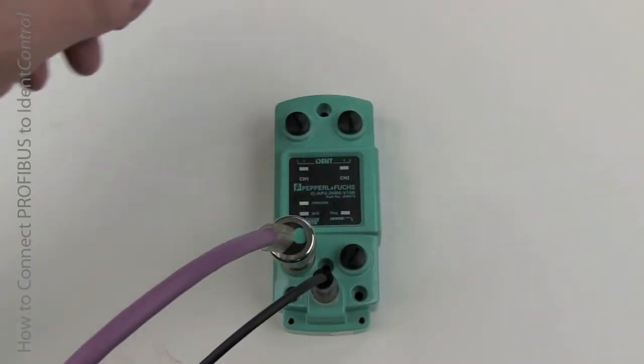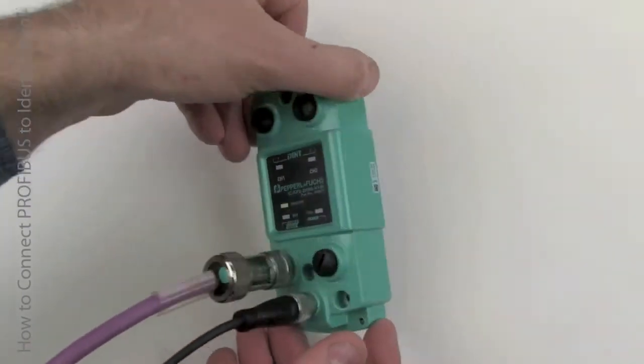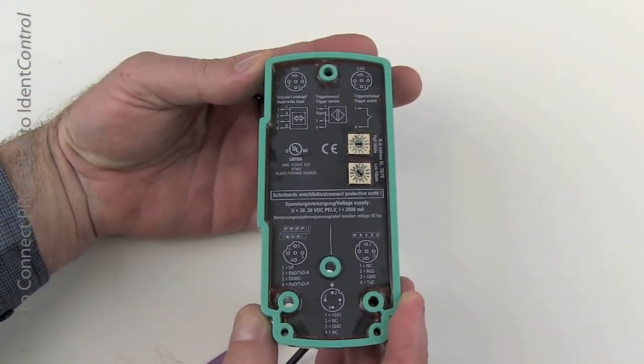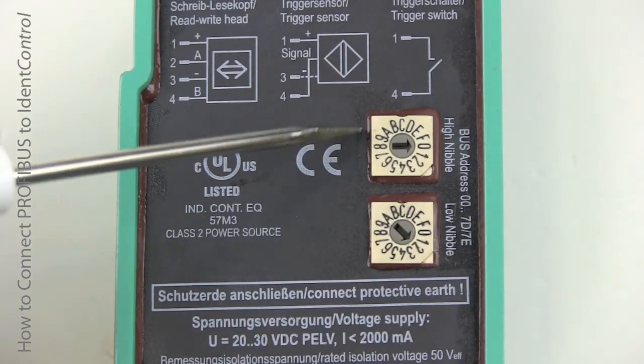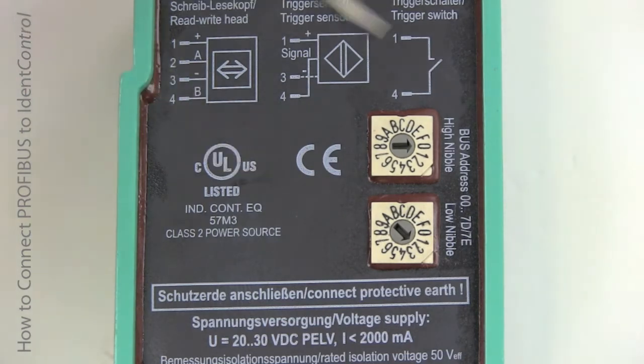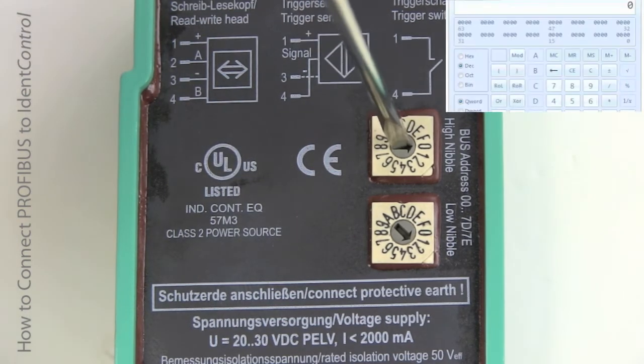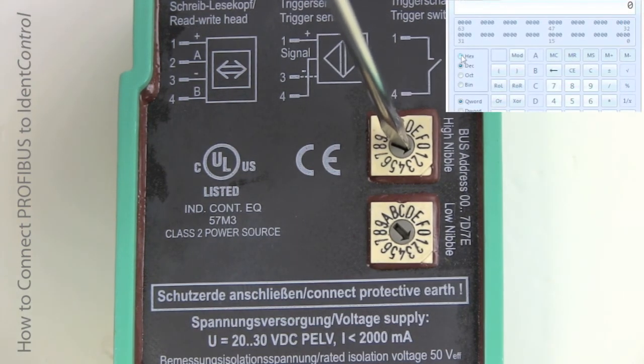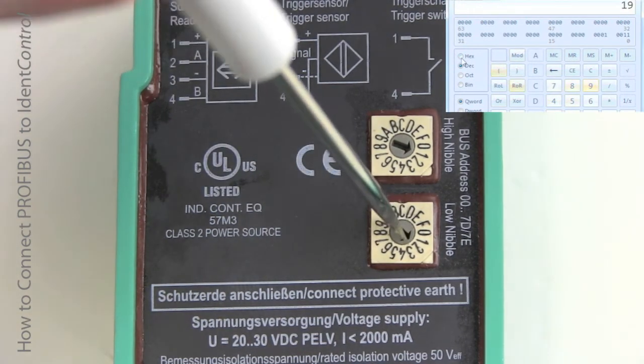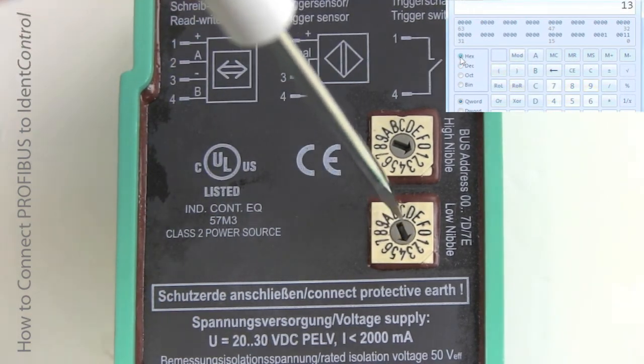On the Ident Control Compact, you'll see there's no display, but if you flip it over, you'll find the two rotary switches that we're going to use to set the address. First thing you have to do is take your address in decimal, convert it to hex, and then you can enter it here as a two-digit number. High byte on the top, low byte on the bottom. In this case, address 19 will be converted to 13 hex.